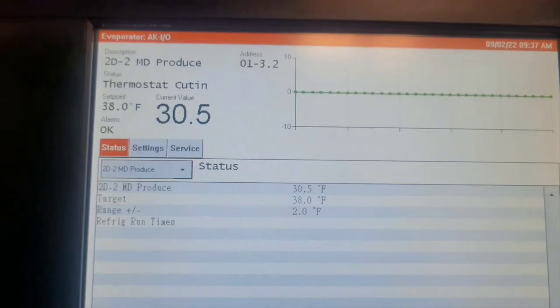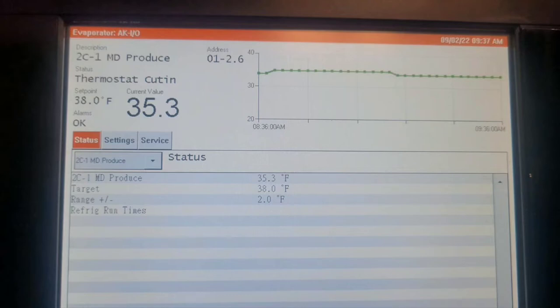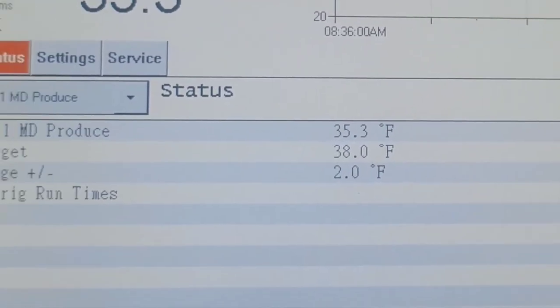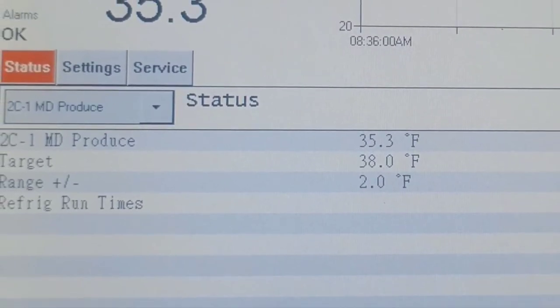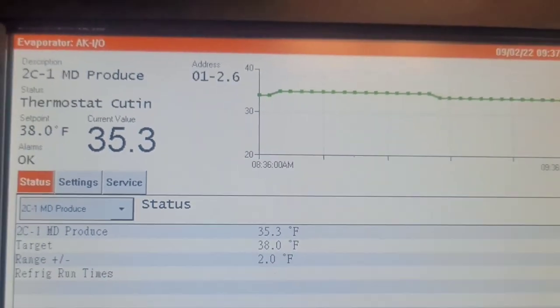Same thing for 2D2, which is really the same circuit. It's set for 38, but for some reason it's getting all the way down to 30. If you look at circuit 2C, which is this one, it has the same thermostat set point but it's doing a little bit better. Down here it has a range plus or minus 2 degrees, so 35.3, that's really close.